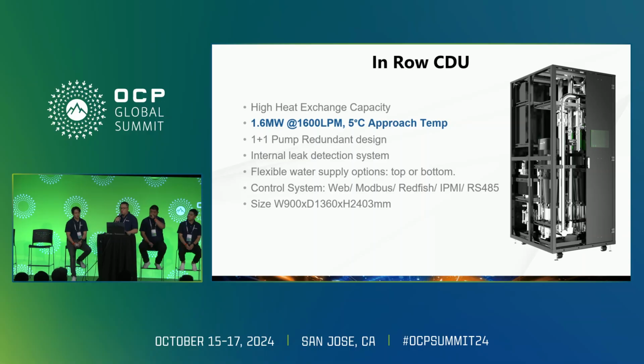For users who have a primary liquid cooling facility, AURAS has the in-row CDU solution. Our in-row CDUs, installed alongside a row of server racks, can provide different levels of cooling capacity. This model can support up to 1,600 kilowatts. Our in-row CDU also equips redundant functions, leak detection system, and compatibility with different control systems.